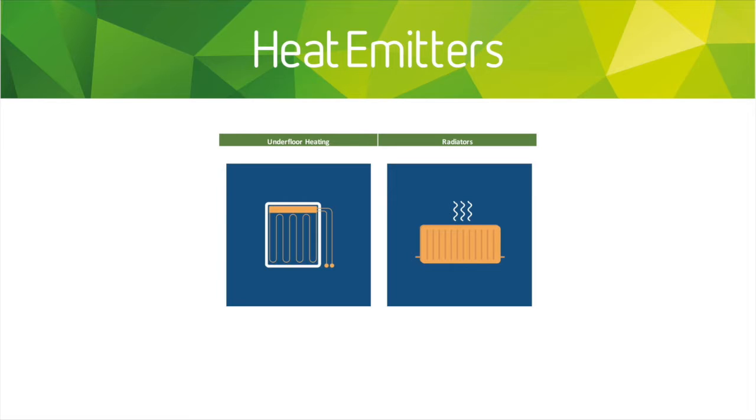They provide sort of heat drafts, because the advantage with radiant underfloor heating is that the air temperature in the space is pretty much constant, and with the heat emitters there's always going to be some form of convection within the space compared to a radiant system. And when they talk about radiant heating and underfloor heating being more efficient, what they actually really mean is you can have a lower internal temperature and you feel a lot more comfortable, and that's where the efficiency comes from.